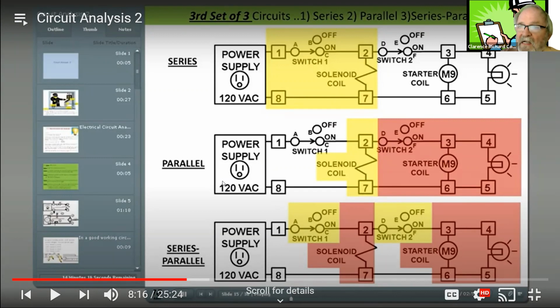And then for our second question, the starter does not energize. This guy right here does not energize. Everything else works just fine. So we check at the starter terminal. Yep, that'd be good. About 92% of you guys did that. Check for 0 on the other side, and 92% of you guys did that as well. Some people said check at terminal 6, 120 volts or for 0 volts.